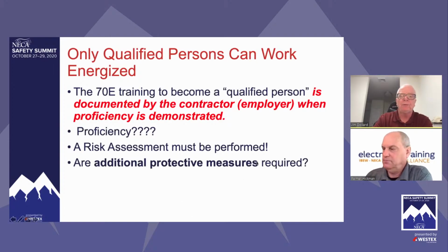And in 2018, we changed things up a little bit. We didn't send you right to the arc flash PPE tables. We didn't send you right to PPE if you've got an incident energy analysis. Now we say if additional protective measures are required, now you go to the hierarchy of risk control. Palmer? Yeah, so we'll start at the most common justified energized work as an example. We're going to cover this a little bit later as well, but voltage testing, troubleshooting, or I would say, hopefully the only justified energized work we're doing is verifying absence of voltage as part of our lockout tagout. So it is not considered electrically safe. It is not considered under lockout tagout until we have verified absence of voltage as one of the steps.